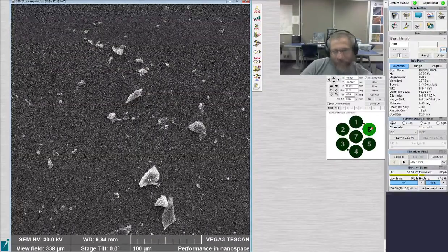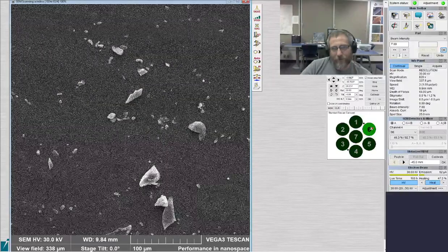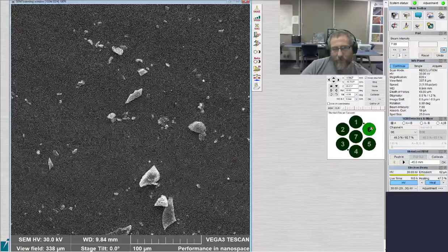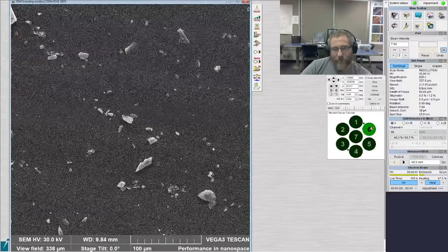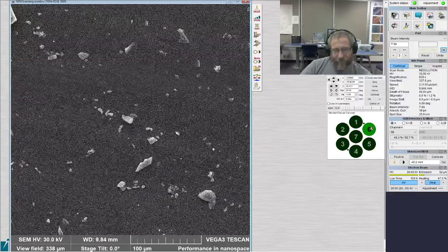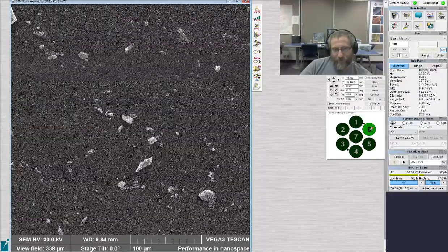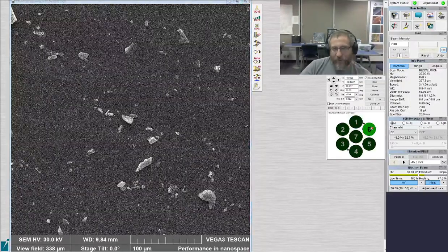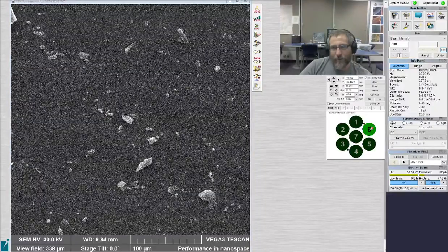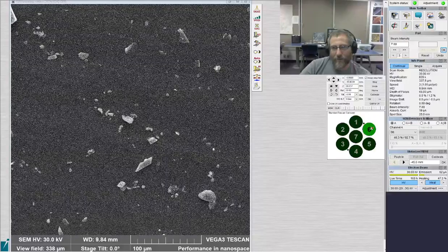If you were to load a carousel up, could you provide the machine with coordinates of where a specimen was, and say, go to stub 6, here are the coordinates, and it'll get pretty darn close? Yes and no. You can see there's a little XYZ thing on the menu here.